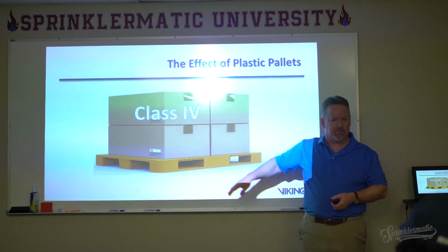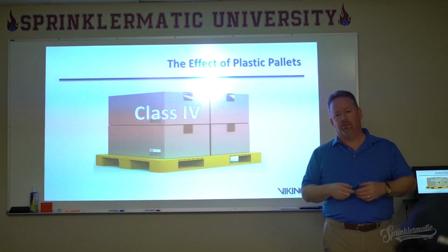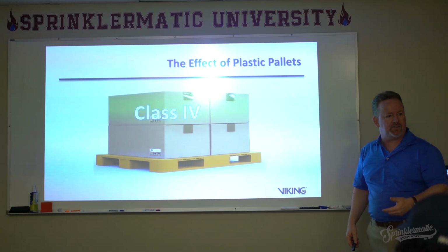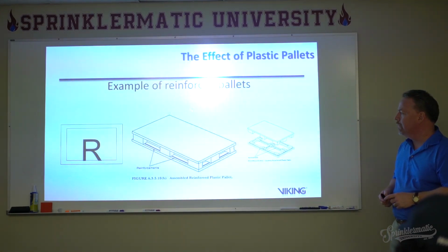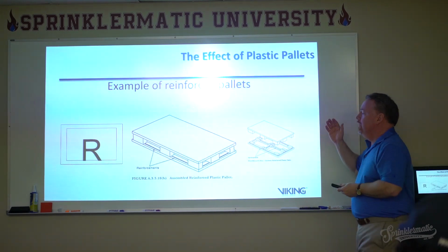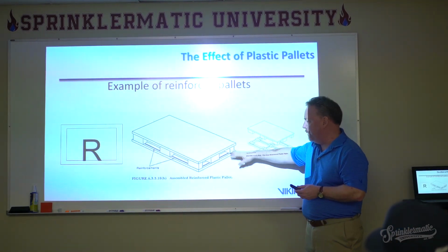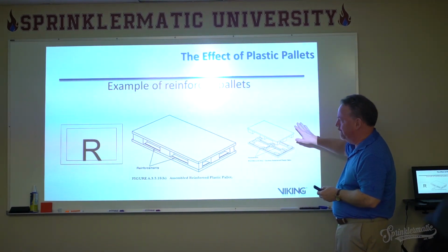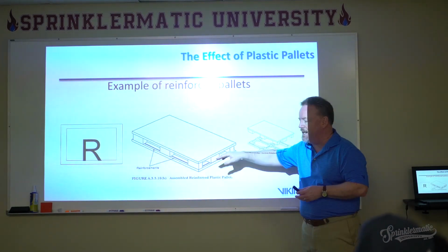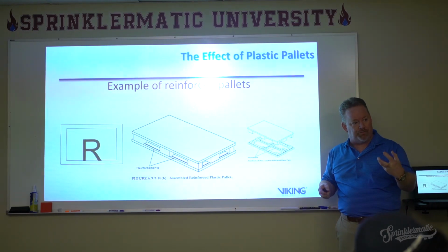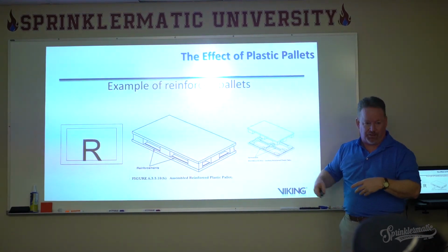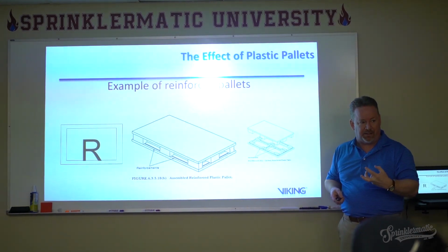and the pallets do. That has an impact. You take a class 2, it goes up to a class 4. Okay, now, the example of reinforced plastic pallets here, basically, what the standard used to say is that you had to have that reinforced plastic, you had to have that particular item on a reinforced plastic pallet.